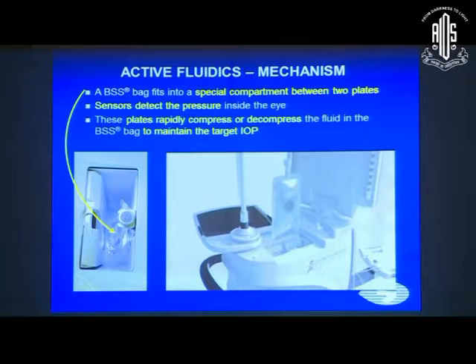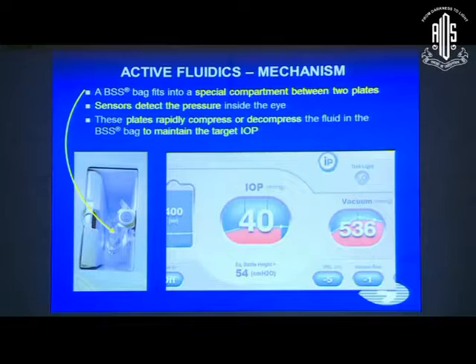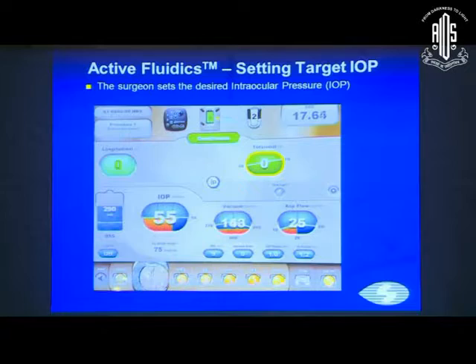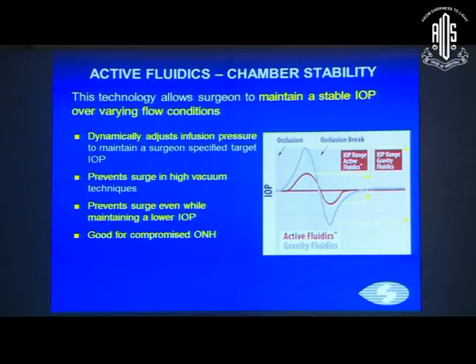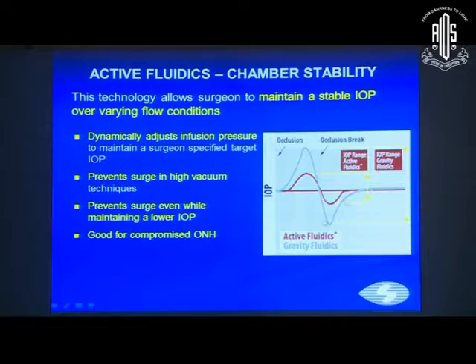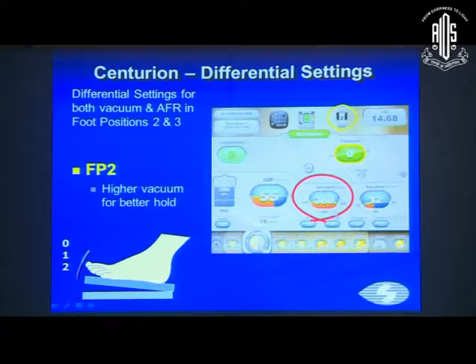In active fluidics, a BSS bag fits into a special compartment between two plates. Sensors detect the pressure inside the eye, and the plates rapidly compress and decompress the fluid to maintain a target intraocular pressure set by the surgeon. This technology dynamically adjusts infusion pressure, preventing surge while maintaining low IOP, and is especially beneficial for the optic nerve head.